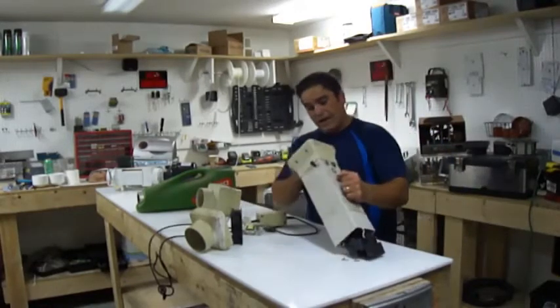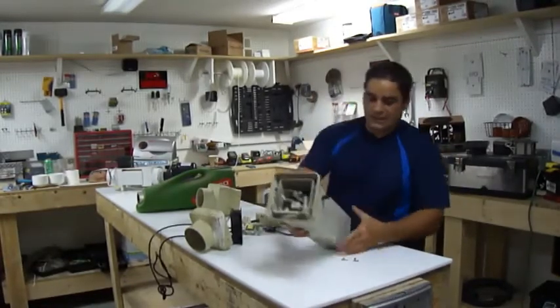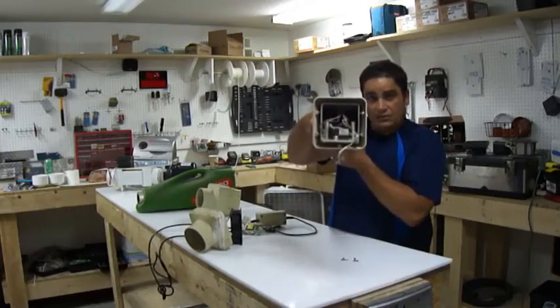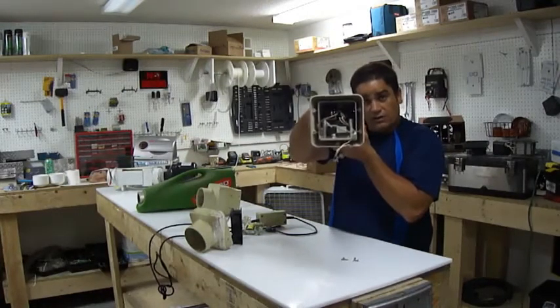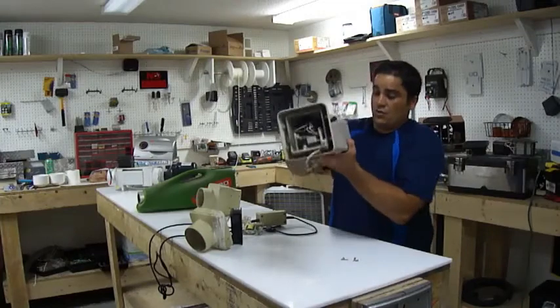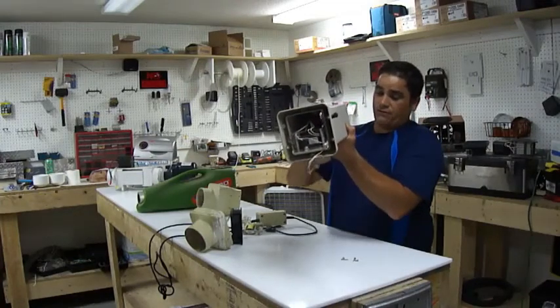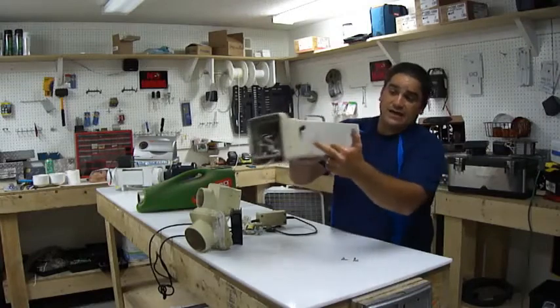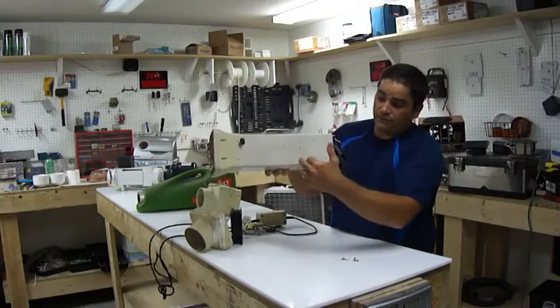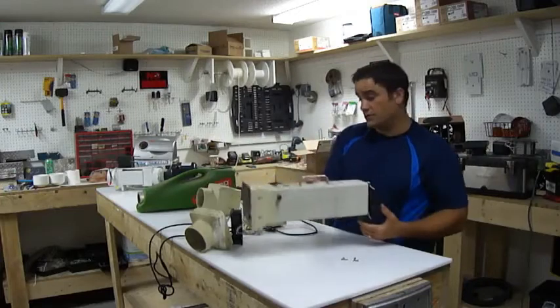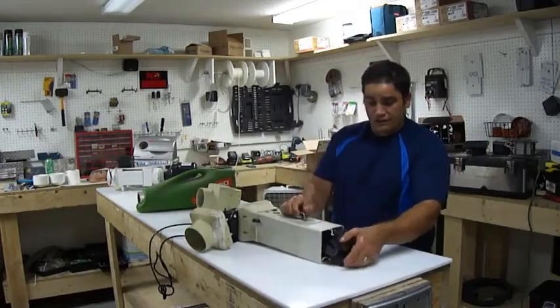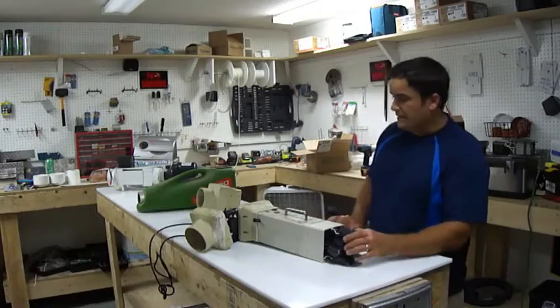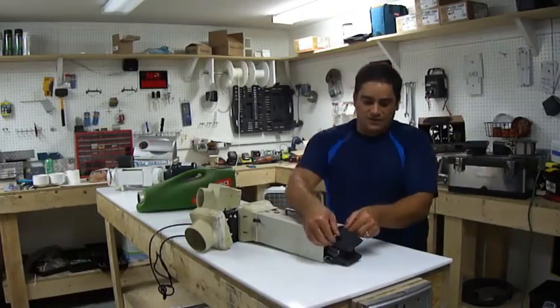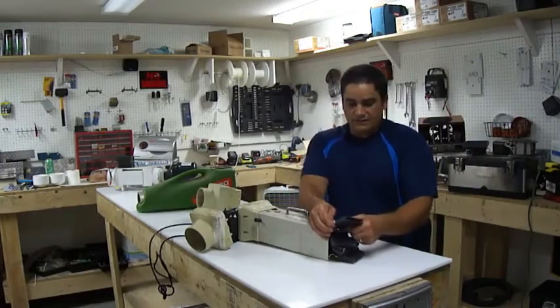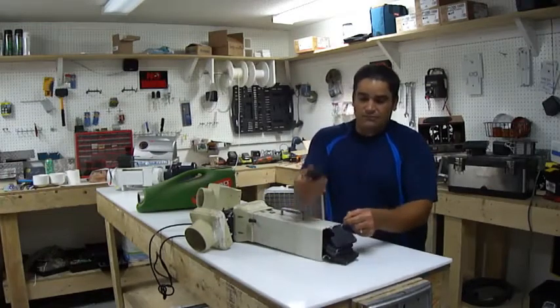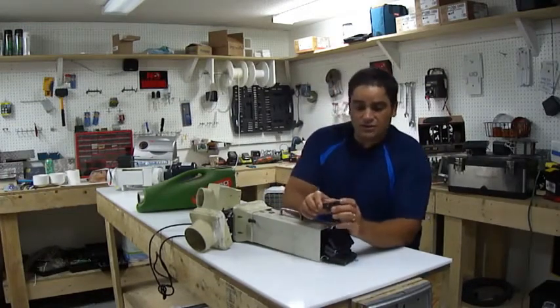Now in the middle, if you can see through here, there's very little room for airflow down this entire length. We've got 1, 2, 3, 4, 5, 6 generator cells, and in here we have 1, 2, 3, 4, 5, 6 transformers. We have one transformer for each generator cell. That's nice, but the generator cells themselves are just a standardized, just another variation on a theme. And I'm going to unplug this generator cell here and show you what's in it.